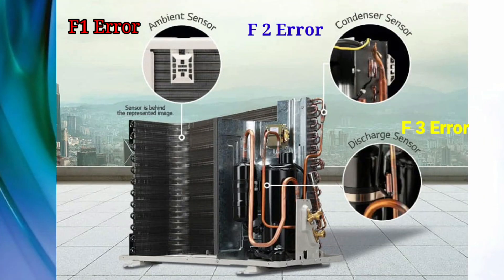This is the complete picture of the outdoor unit. One is the ambient sensor — that's the F1 error. Another is the condenser sensor — that's the F2 error. And the third is the discharge sensor — that's the F3 error. So if fault F1 appears, check your ambient sensor; for F2, check your condenser sensor; and for F3, check your discharge sensor. Thanks for watching — please like and subscribe to my channel!